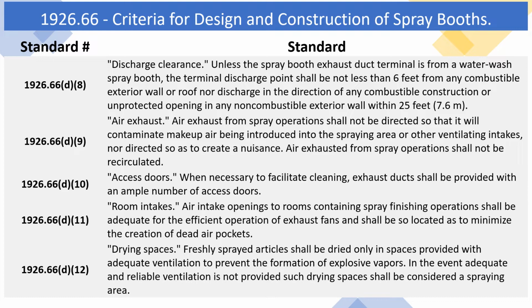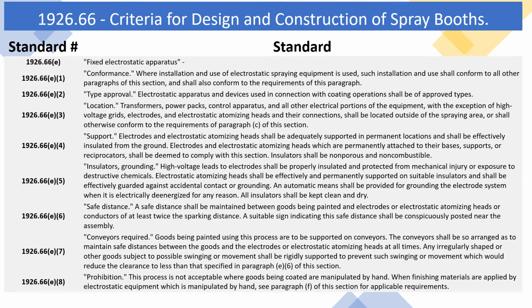1926.66 D12. Drying spaces. Freshly sprayed articles shall be dried only in spaces provided with adequate ventilation to prevent the formation of explosive vapors. In the event adequate and reliable ventilation is not provided, such drying spaces shall be considered a spraying area. 1926.66 E. Fixed electrostatic apparatus. 1926.66 E1. Conformance. Where installation and use of electrostatic spraying equipment is used, such installation and use shall conform to all other paragraphs of this section, and shall also conform to the requirements of this paragraph.